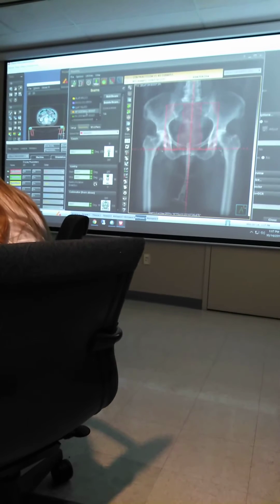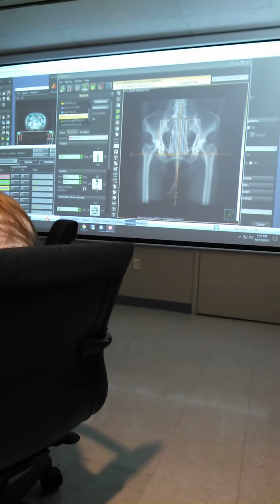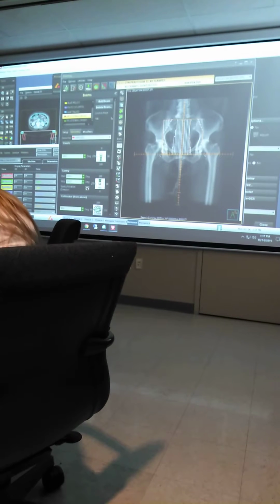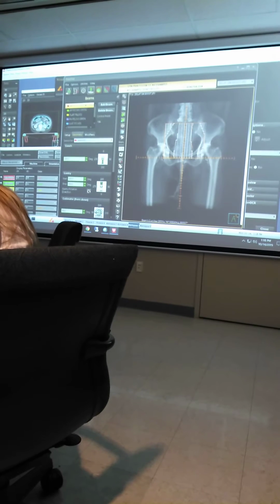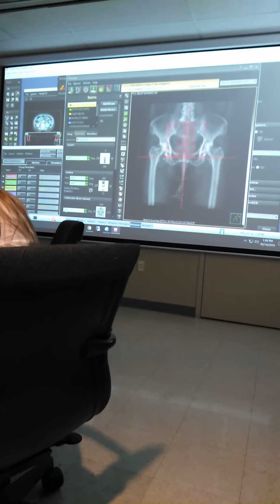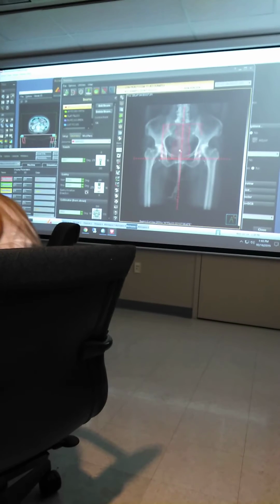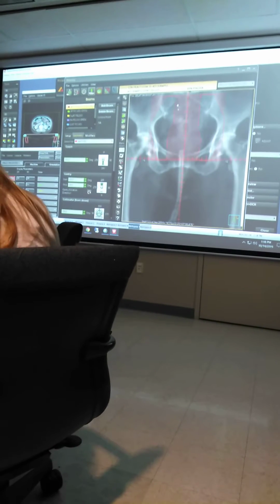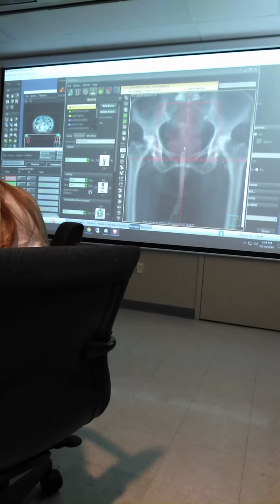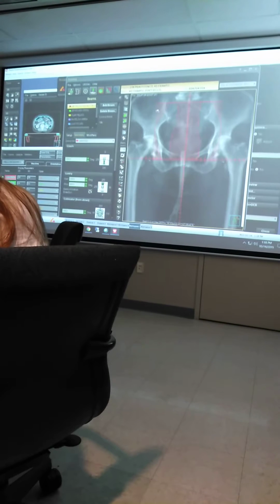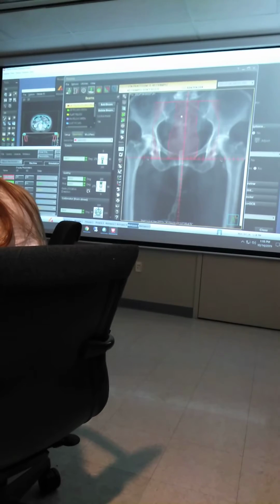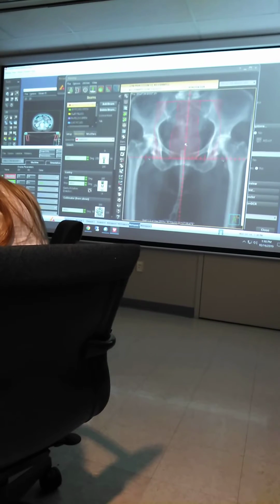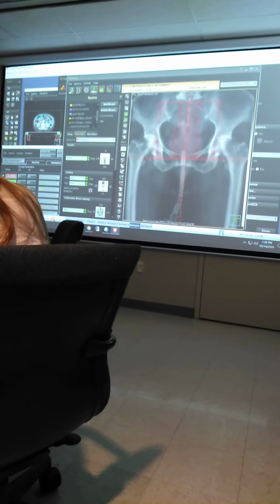And once you copy it, I would say also before copying, you want to rotate your collimator 90. It's 180. But the thing is, you can't have leaves coming through the middle here, right? So in order for leaves to come in through, your leaves have to come and swoop in. Otherwise, you're only going to have leaves blocking here laterally, and you can't block in here. So you got to rotate your collimator so that the leaves come and swoop in. Okay.